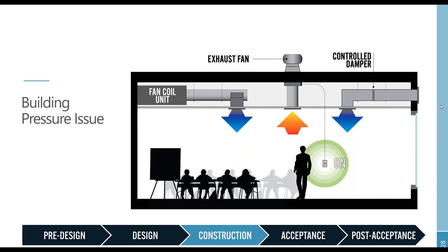So when we were on site early on, we did a spot check and we turned the exhaust fan on, and we discovered that no air was coming in through this controlled damper. So we brought this up to the mechanical contractor and alerted them that the motorized damper probably wasn't wired correctly or wasn't working correctly just yet. A couple months later, when the project was ready for turnover, we came back in and repeated the same test, and all worked well.